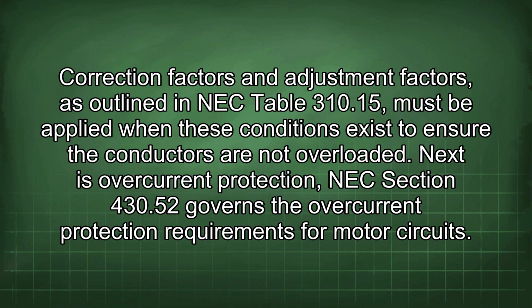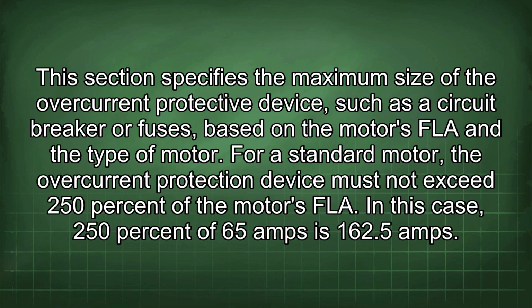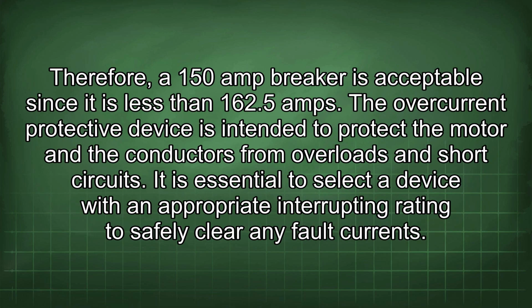Next is overcurrent protection. NEC section 430.52 governs the overcurrent protection requirements for motor circuits. This section specifies the maximum size of the overcurrent protective device, such as a circuit breaker or fuses, based on the motor's FLA and the type of motor. For a standard motor, the overcurrent protection device must not exceed 250% of the motor's FLA. In this case, 250% of 65 amps is 162.5 amps. Therefore, a 150 amp breaker is acceptable since it is less than 162.5 amps.